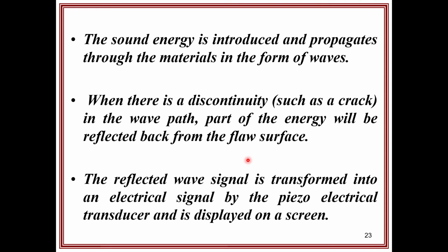Inside the material, if there is any crack or hole present, the ultrasonic waves will reflect back, and the remaining sound waves will travel to the end of the material and reflect from the back portion of the material. We'll see that the reflected wave signal is transformed into an electrical signal by the piezoelectric transducer and is displayed on the screen.